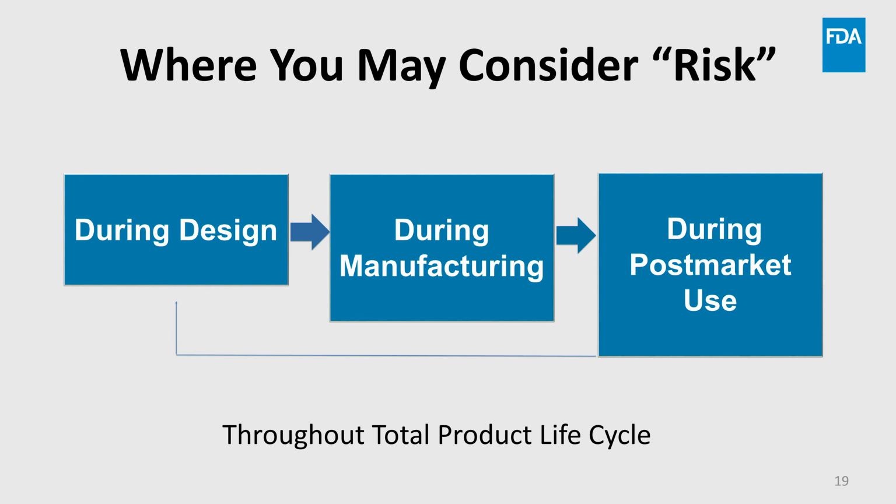Here are some of the places you may be looking at risk, making risk-based decisions, and using risk analysis techniques, and performing risk management. Risk is something that occurs throughout and encompasses the total product life cycle. It also loops back as more information about the medical device becomes available. You will start by determining risk during device design.